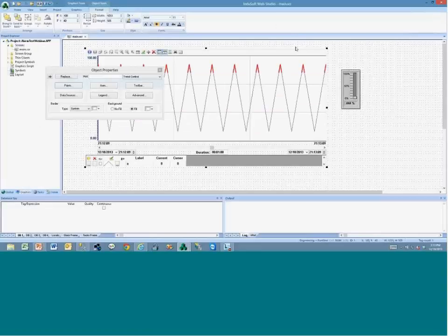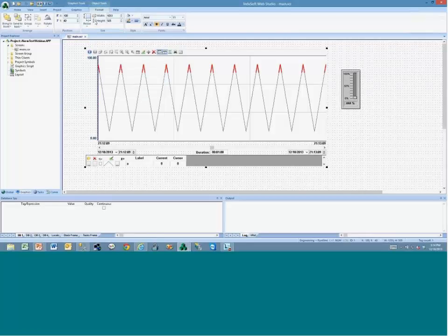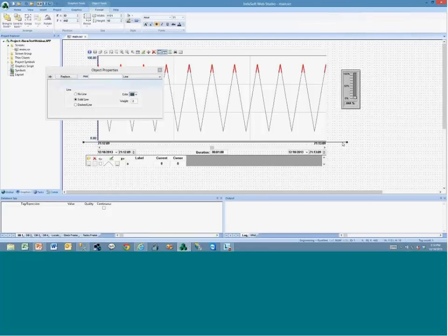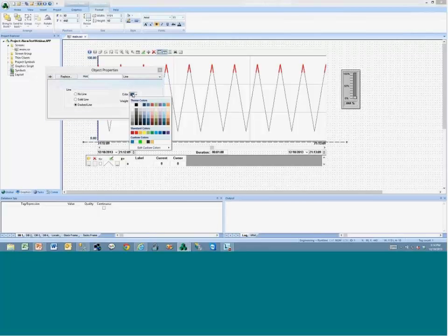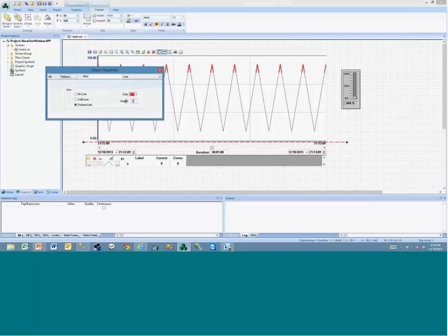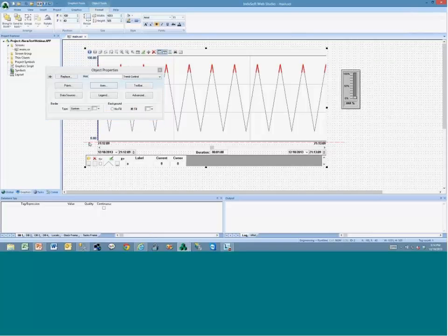Another way would be to show a horizontal line on the alarm limits, which is possible as well, either creating a pen, another pen only for the lines, or when the limits are very well defined and do not change drastically from pen to pen, an easy way to accomplish it is to create a horizontal line on the screen. And you can define here the look and feel for the line, the color for the line, the thickness and everything. So you create a horizontal line, and you define here the Y position for this line right here is 40.